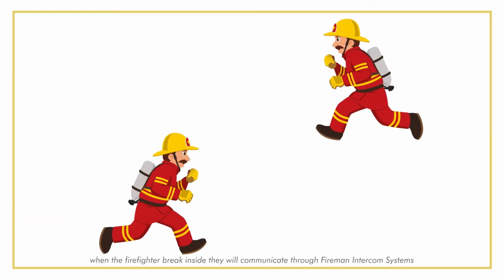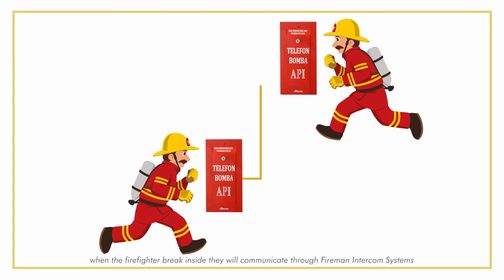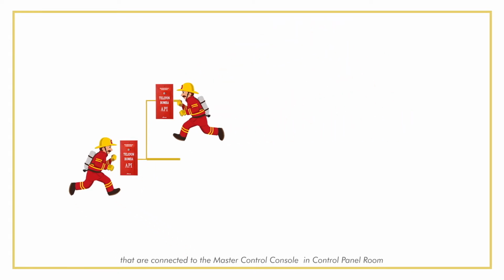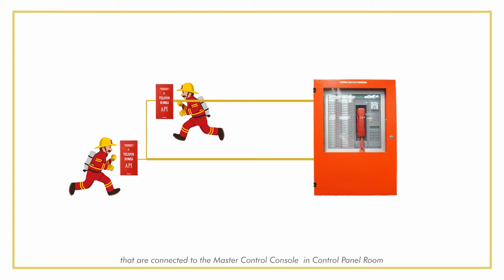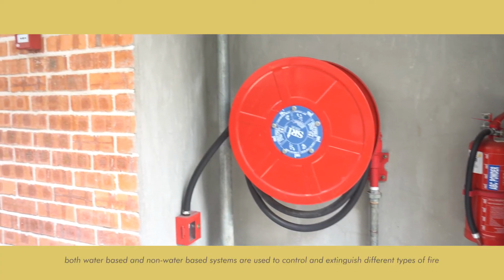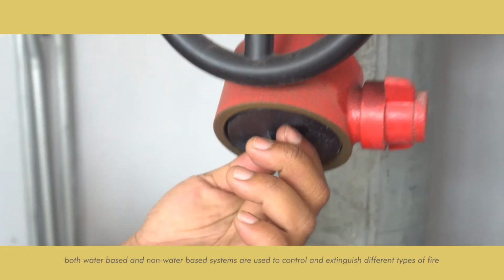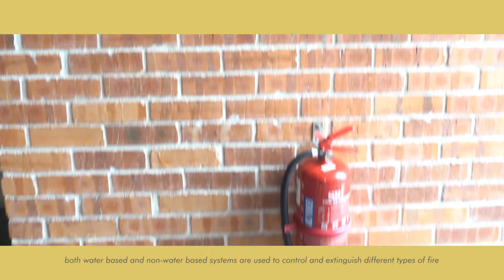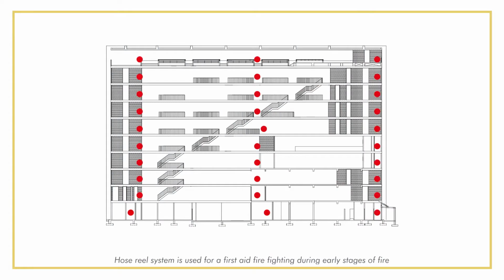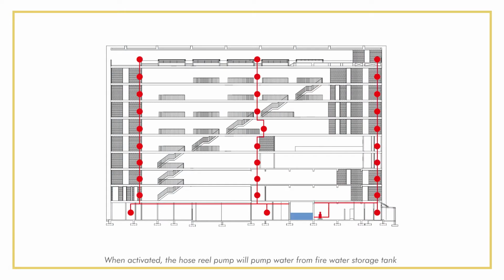When the firefighters break inside, they will communicate through fireman intercom systems that are connected to the master control console in the control panel room. Both water-based and non-water-based systems are used to control and extinguish different types of fire. The hose reel system is used for first aid firefighting during the early stage of fire. When activated, the hose reel pump will pump water from the fire water storage tank to the hose reels located at both ends of the building and at the middle of hallways.